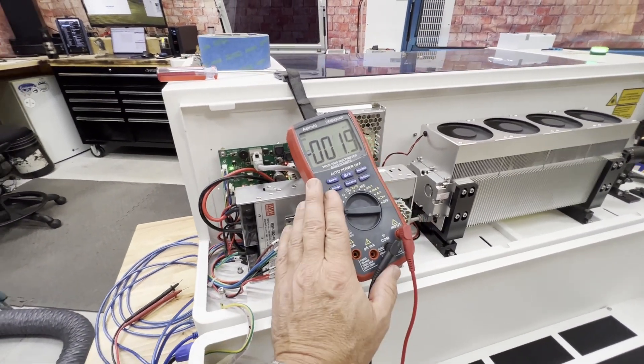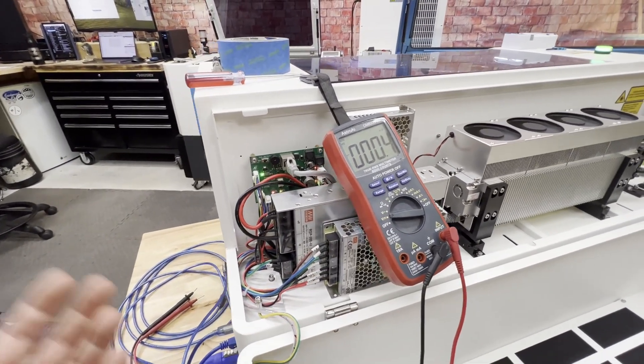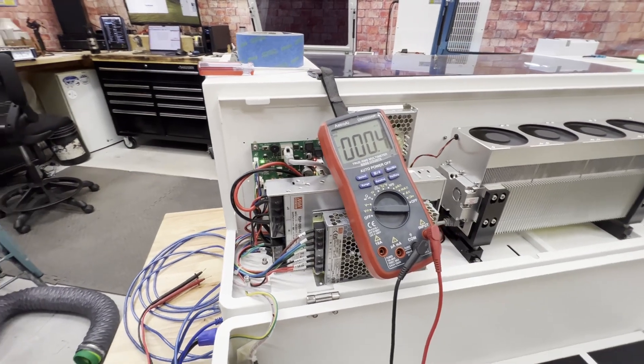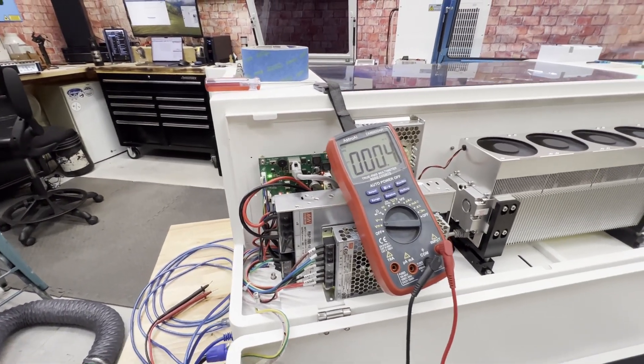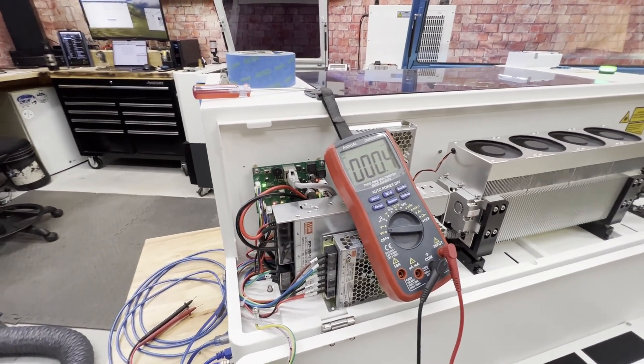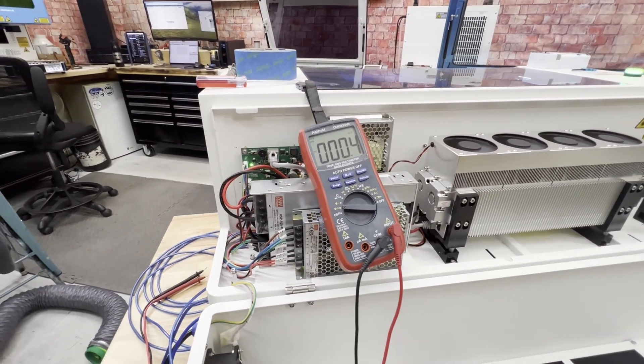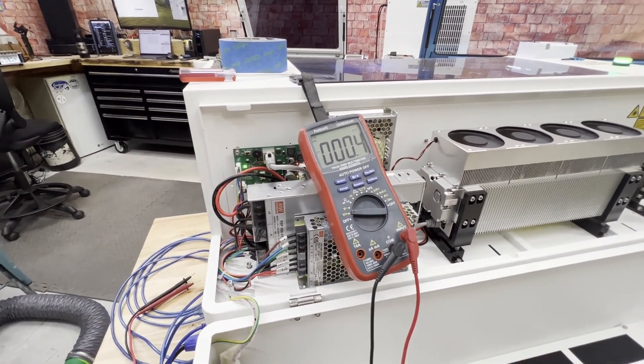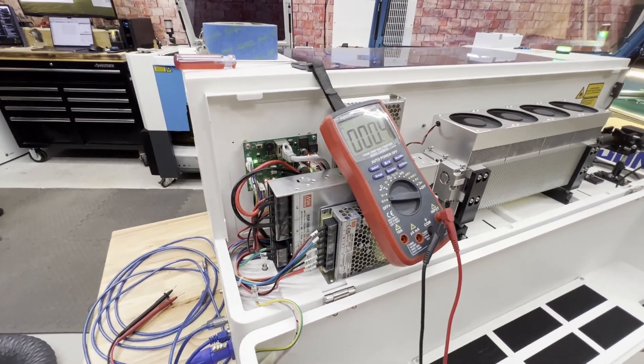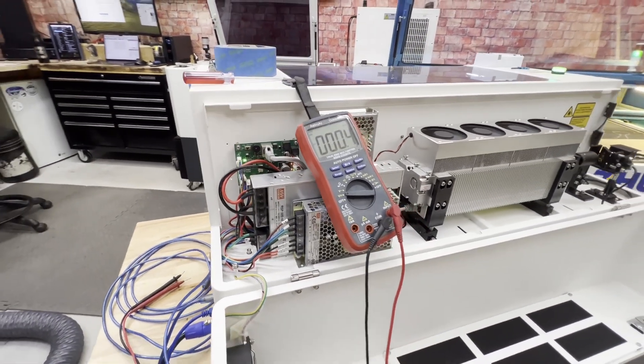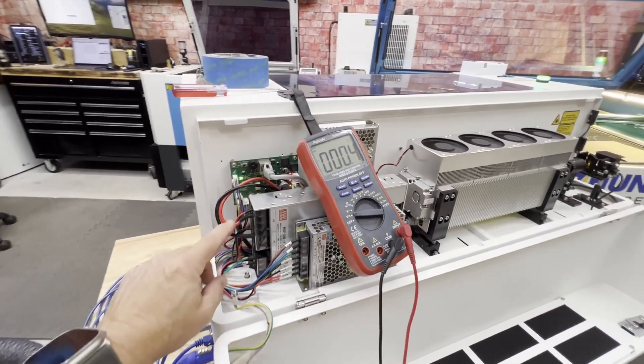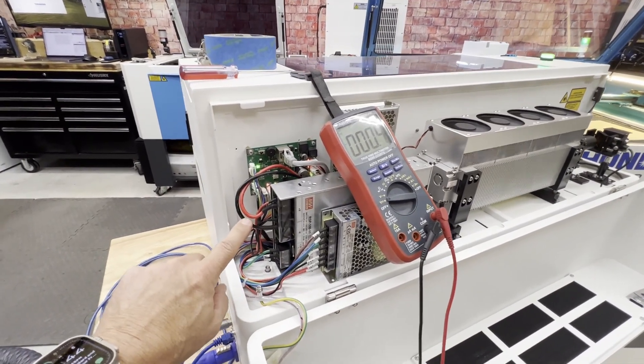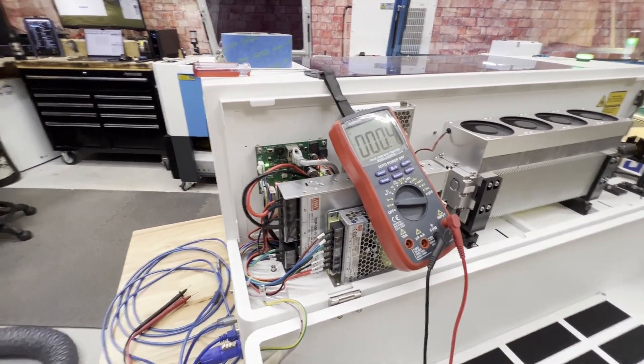So what we're going to have to do with a multimeter is test to see what type of voltage we're getting. It should be nominally right around 48 volts, not much lower, not much higher. It can fluctuate a little bit depending on your incoming source, but we will have to test our positive, which is our red, and our negative leads to see how much voltage we're getting out.